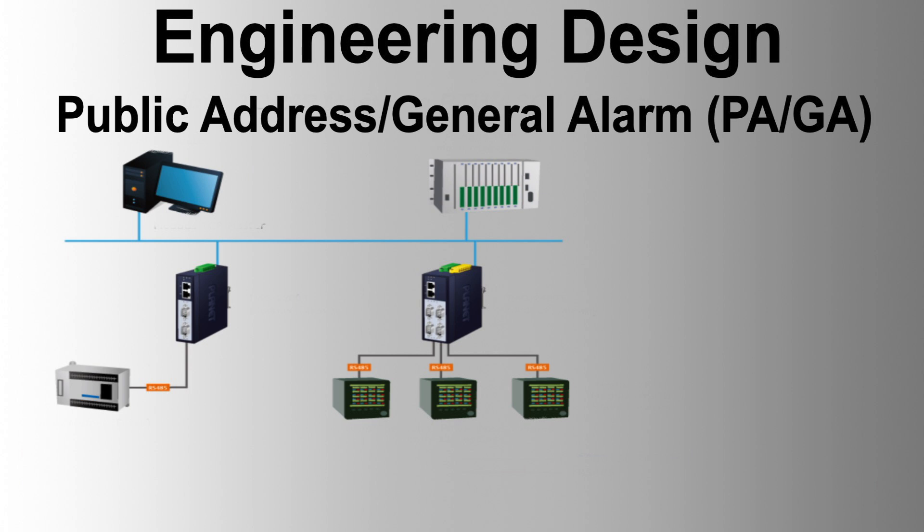PAGA system hardware – cabinet: the PAGA system cabinet houses controllers, power amplifiers, alarm tone and message generators, and interfaces to the fire and gas system, the PBX system, and the SDH FO communication system for remote connections. The standard cabinet is a RITTAL TS8, 2000 mm × 800 mm × 800 mm, with a swing-type 19-inch rack frame, dual access, lockable doors, and a 100 mm ventilated plinth. Accessories include a 19-inch industry-standard mounting frame, power distribution system, cable management system, removable shelves, earthing kit, washers, grip nuts, low-noise ventilation fans, and ventilation louvers.